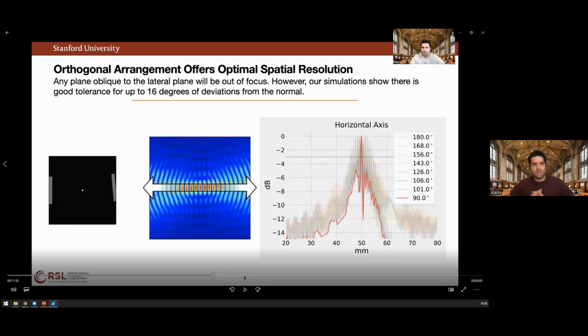I'm afraid not, because with a single element transducer, we are still going to face the aberrations due to the skull, and we need to account for those. A single transducer is not going to be able to do that. So for that scenario, we need phased arrays so that we can time the transducer elements accordingly. On the slide where I showed the sheep skull, that's an example of this, where we had to actually use phased array transducers to account for the aberrations.